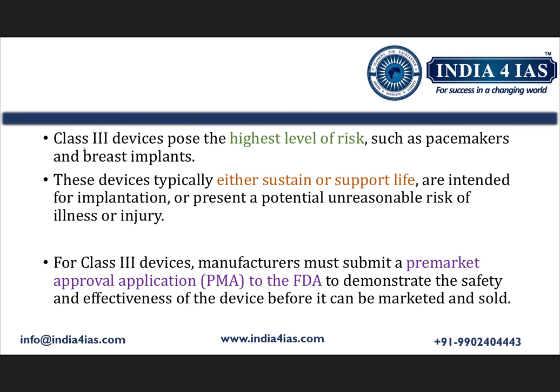The reason being, class 3 devices pose the highest level of risk. Other examples for class 3 devices are pacemakers and breast implants. These class 3 devices either sustain or support life, and also they present a potential unreasonable risk of injury to life. So because of that, they need a pre-market approval and additional safety controls.